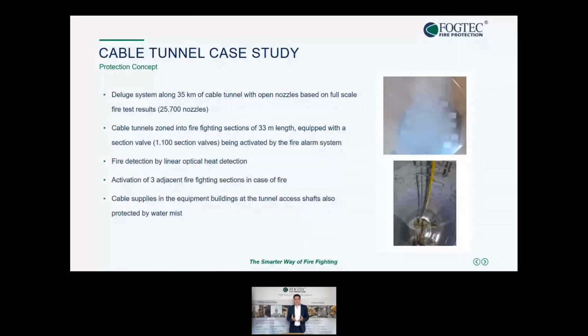At the end, it resulted in a system with around 25,700 nozzles, where we had separated all the areas into sections of 33 meters length, with 3 areas discharged at the same time. In these main tunnels, you only had a ceiling installation.